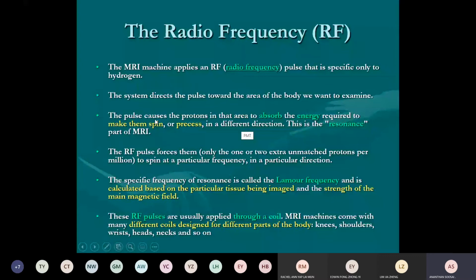So you see the RF pulse. The RF pulse makes them spin at a particular frequency. The specific frequency is called the Larmor frequency, and it's calculated based on the type of tissue and the magnetic field strength. The RF pulses are usually applied through a coil. MRI machines come with different coil designs for different parts of the body. Knees have a different RF coil, shoulders have a different RF coil, and so on.